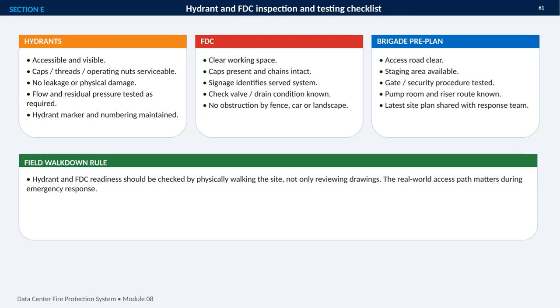This checklist focuses on 3 connected elements of fire department access: hydrants, the fire department connection, or FDC, and the brigade pre-plan. For hydrants, I'm looking for more than simply confirming their location. They need to be accessible and visible, with serviceable caps, threads, and operating nuts. I also need to verify there is no leakage or physical damage, and that flow and residual pressure testing is completed when required. Markers and numbering should remain clear and maintained.